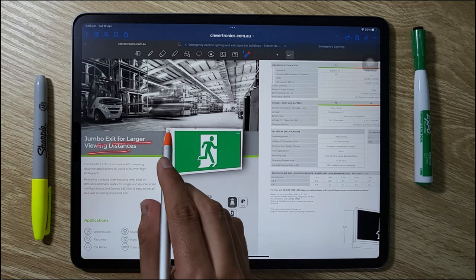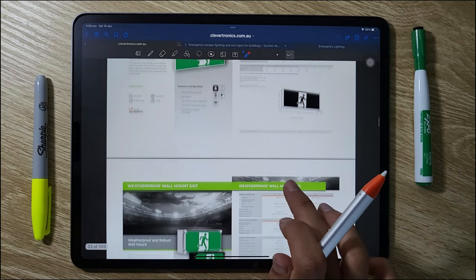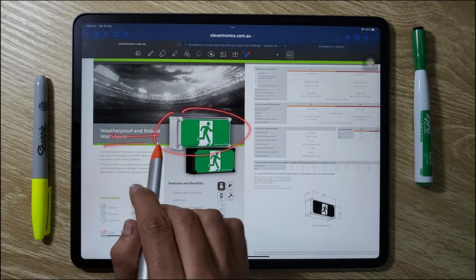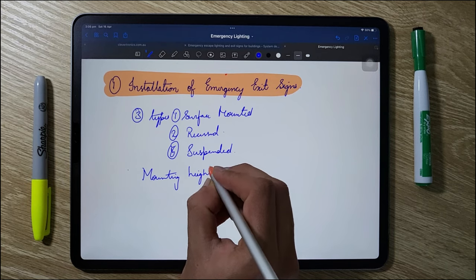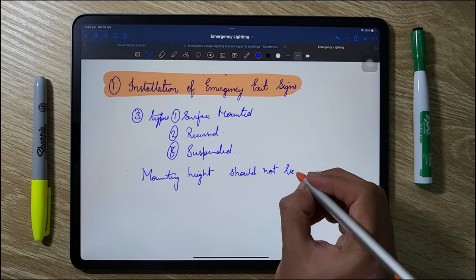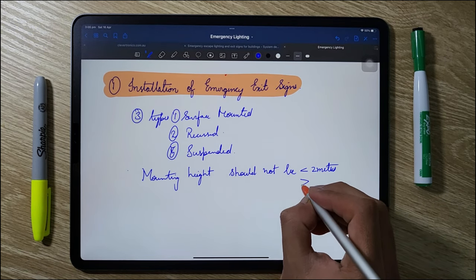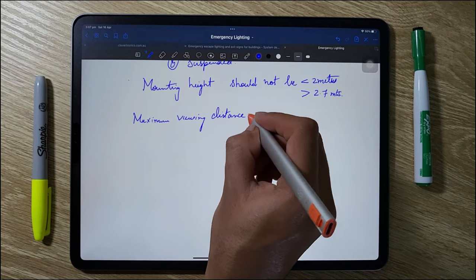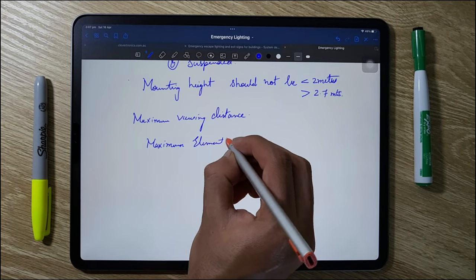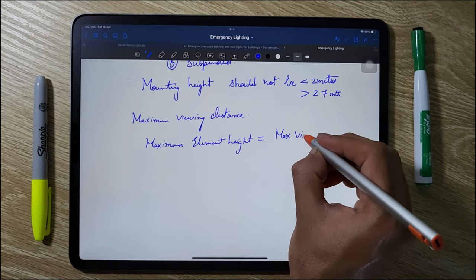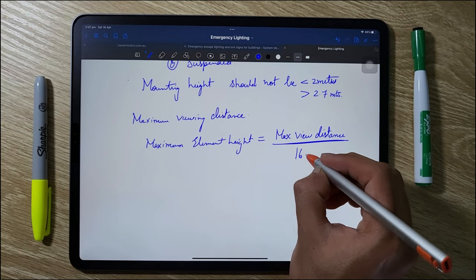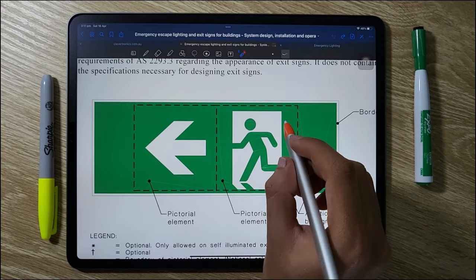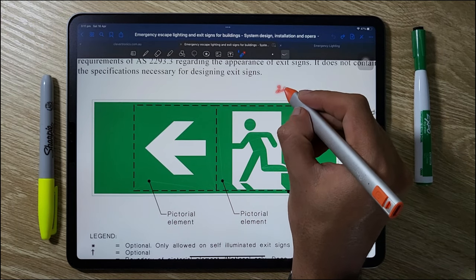There are also jumbo-size emergency exit signs that provide a maximum viewing distance of more than 50 or 100 meters, applicable to airports, warehouses, or factories. As per AS 2293 standards, the mounting height of emergency exit signs should not be less than 2 meters and not more than 2.7 meters. To calculate the maximum viewing distance, the formula is: maximum element height = maximum viewing distance divided by 160. For a maximum viewing distance of 32 meters, dividing 32 by 160 gives an element height of 200 mm.